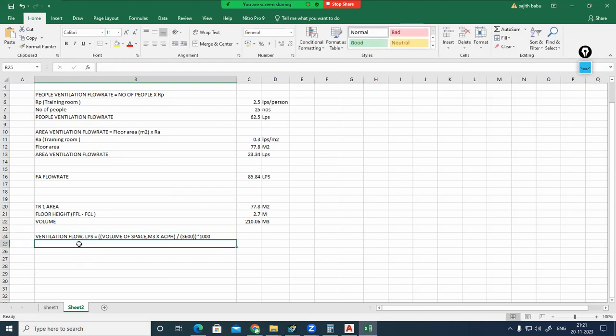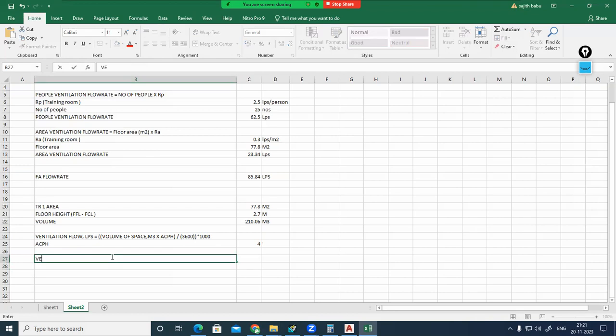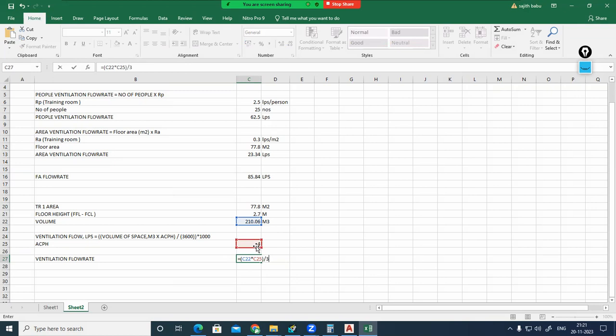By that consideration, for example, air changes per hour, if it's training room one only, we need, say for example, 4 air changes per hour. Then the ventilation rate of flow will be volume of space multiplied by air changes per hour, divided by 3600. So you'll be getting that in meter cube per second. Multiplied by 1000, you can convert that into liter per second. Correct, 1 meter cube is 1000 liter. Click enter. You'll be getting 233.4 liter per second of air. So this will be the air changes per hour method.